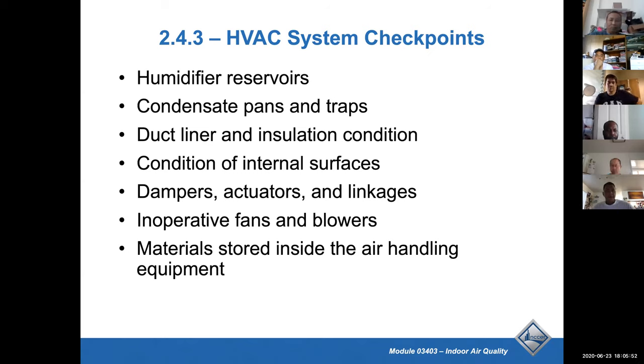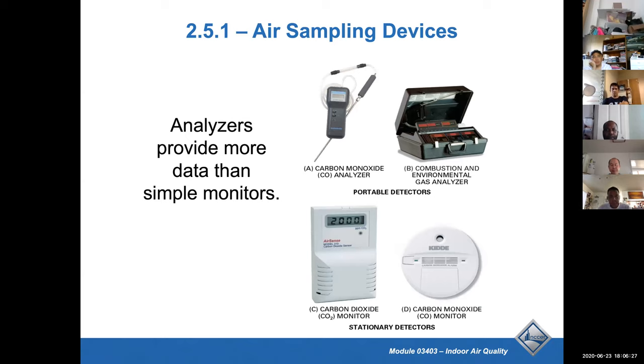This talks about checking the HVAC system. Humidifier reservoirs, because they can build up algae and mold, mildew. Condensate pans and traps, same thing. Duct liner, insulation condition. Condition of the internal surfaces, dampers, actuator linkages, inoperative fans or blowers. You get a fan that's not working, it could cause a problem. And material stored inside the air handling equipment. Oh, that's a good one. Okay. Here's different air sampling devices.